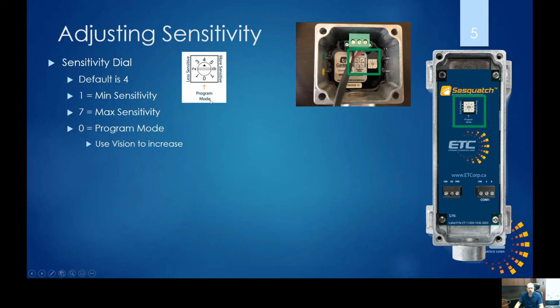0 is a special mode called program mode. You can see that in all these cases here. This allows us to interact with these sensors using Vision. And so from a sensitivity perspective, we can actually increase the sensitivity beyond what's available on the sensitivity dial. And we do have a support article on how to do that. By default, though, we don't use the maximum sensitivity that's available, because very, very small changes could trigger the sensor. And so we kind of have reserved this as a special feature.